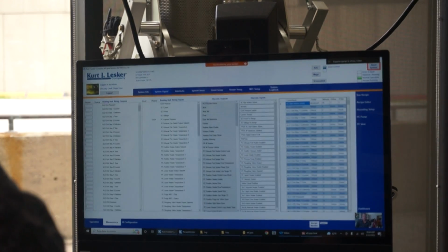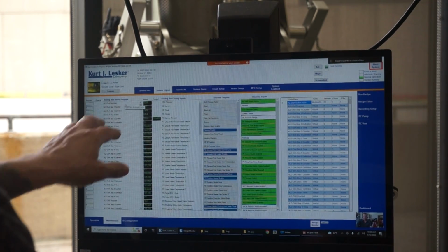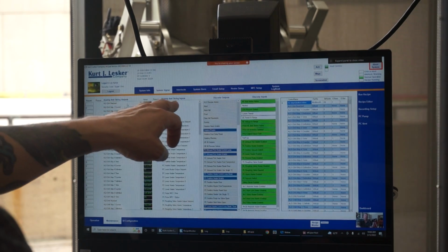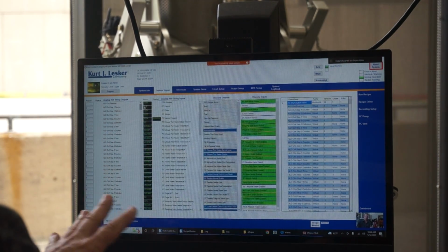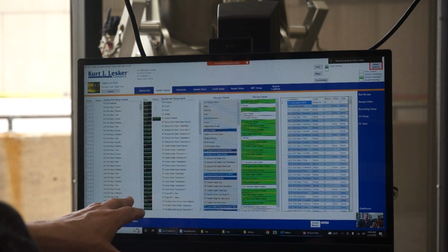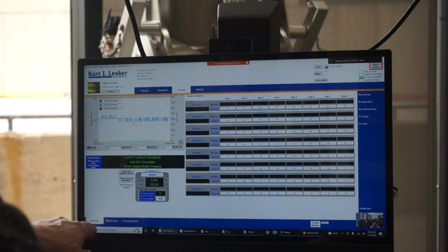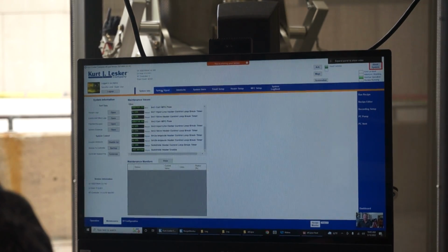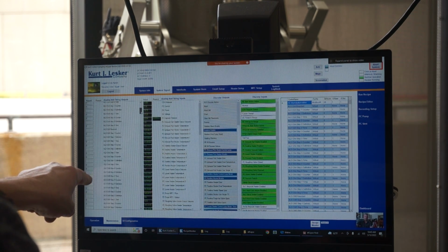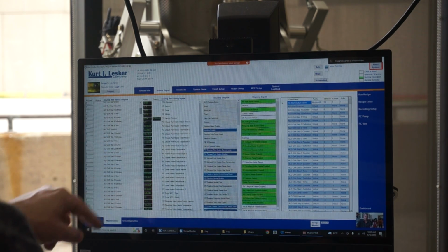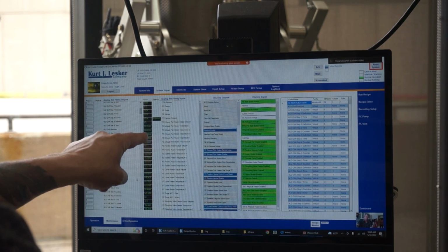System signal tab, you can come in, and your analog string outputs, inputs, discrete outputs, and discrete inputs are here. This is more information under the maintenance than you see under operation. Maintenance is a lot more information. You can scroll down, depending on if it's an output or an input. You can set the output, you can monitor the input.